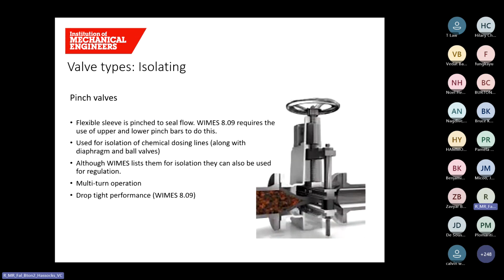Another isolation valve type is the pinch valve. The pinch valve uses a flexible sleeve, which is pinched from the top and the bottom to provide a seal. They're used for isolation of chemical dosing lines, along with diaphragm valves and ball valves. You can also use them for regulation. They are multi-turn valves, and they have drop-tight performance.